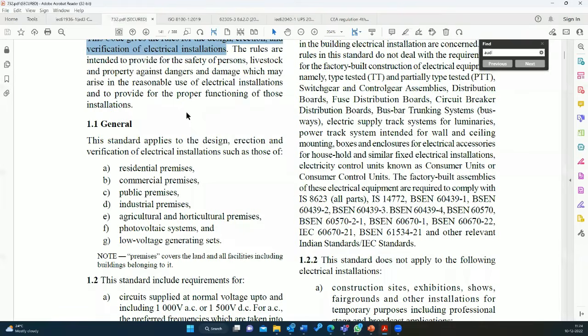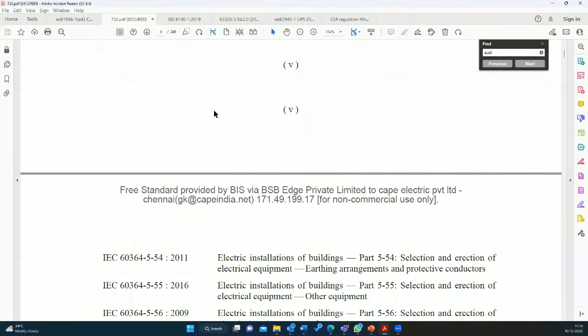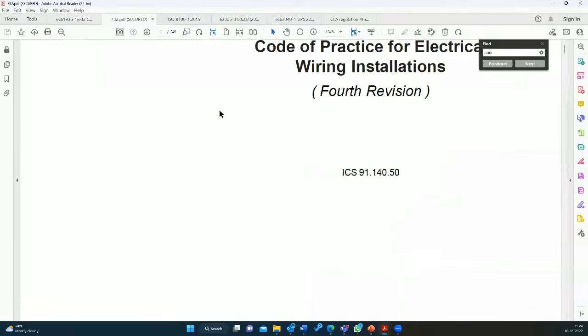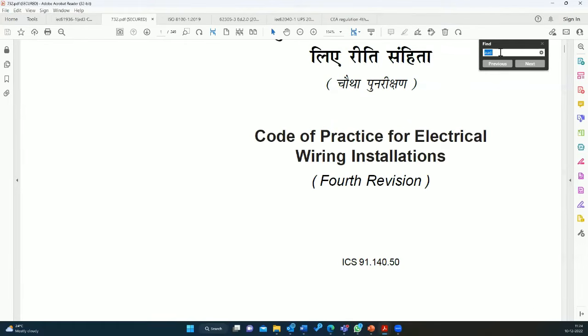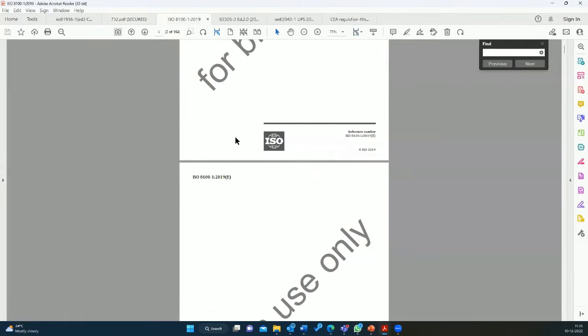I'm just showing you also the standard IS 732. All of you know it very well. Nowadays, we talk more about IS 732, Code of Practice for Electrical Wiring. This is the Indian standard. And here also, I am checking the word audit. There is no word called audit in this particular standard. Whereas if you look at the word verification, it is reflecting in almost 77 places. Similarly, I am showing you the ISO standard for lifts. Audit is never there. Only the word audible is there. Whereas if you look at verification, verified and verification, there are 24 places where verified is used and 18 places where verification is used.